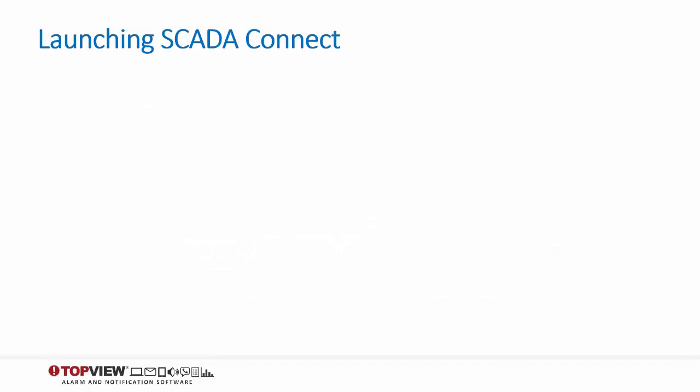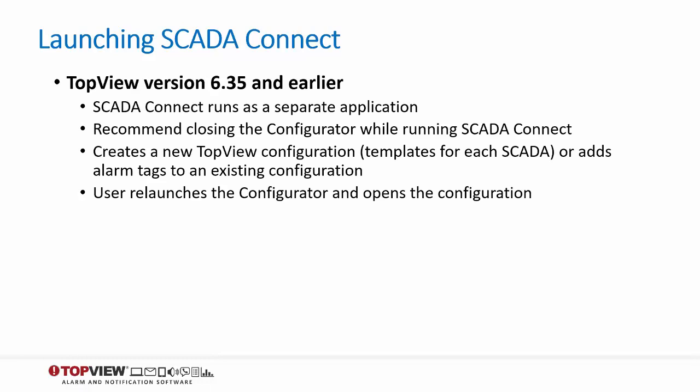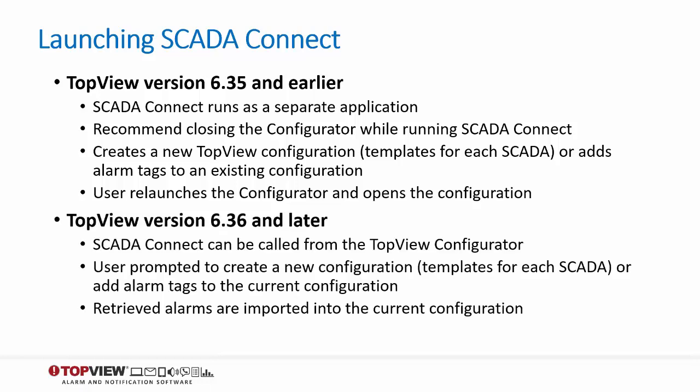Starting with version 635, SCADA Connect is installed with Top View. For earlier versions, the Top View download page contains links to download and install SCADA Connect. In Top View 635 and earlier, SCADA Connect runs as a separate application. Because SCADA Connect may make configuration changes to Top View, we recommend closing the configurator while using SCADA Connect. SCADA Connect will retrieve the SCADA alarm information and either create a new Top View configuration or add tags to an existing configuration. Once it completes, the user can open the updated configuration in the configurator. In Top View 636 and later, the user can run SCADA Connect without leaving the configurator. They can choose to add SCADA alarms to the existing configuration or to create a new configuration based on templates for each SCADA. The retrieved alarms are then imported into the configuration.